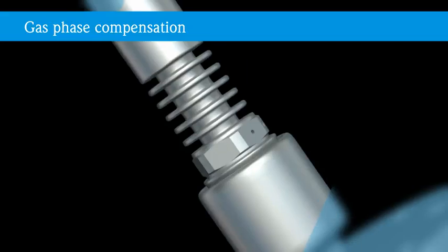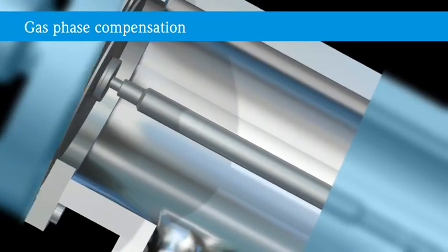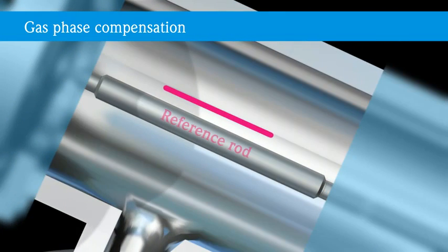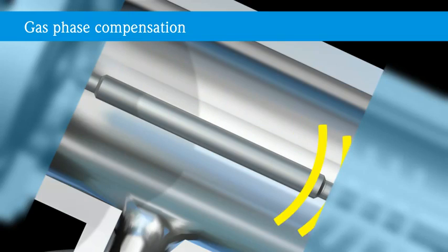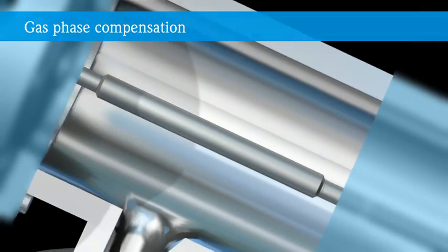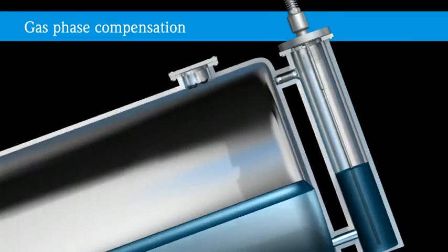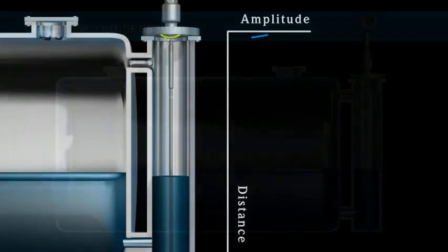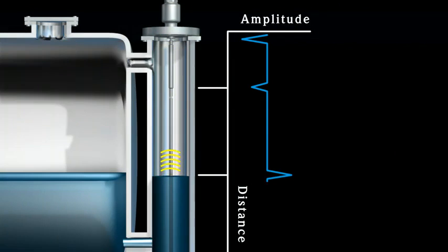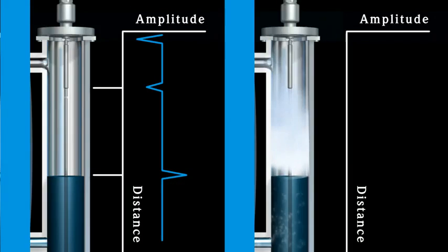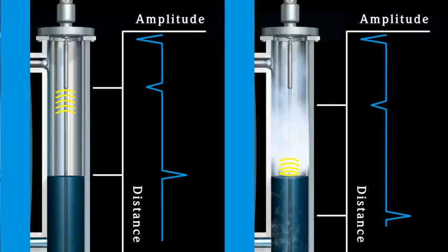LevelFlex M with active gas phase compensation uses a reference signal at a known distance to compensate for the delay and speed of propagation of the microwave pulse measuring the water level. This is done dynamically. For example, when the reference pulse signal shows a small shift in time, the level signal will be compensated proportionally.